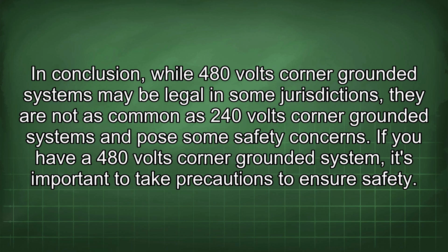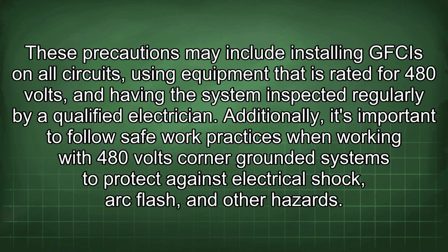In conclusion, while 480 volts corner-grounded systems may be legal in some jurisdictions, they are not as common as 240 volts corner-grounded systems and pose some safety concerns. If you have a 480 volts corner-grounded system, it's important to take precautions to ensure safety. These precautions may include installing GFCIs on all circuits, using equipment that is rated for 480 volts, and having the system inspected regularly by a qualified electrician.